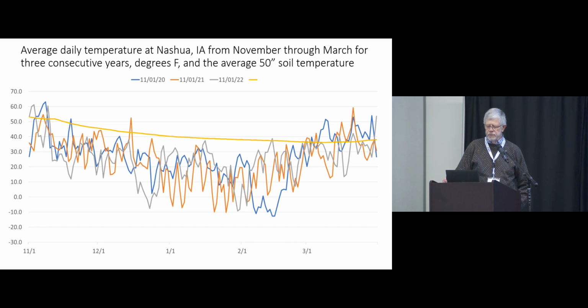And if you had a line for 8 foot, it would be parallel and a little bit above that, but up around 50 degrees there. In Nashua, probably 49 degrees. If you went down to 30 feet, it would be constant. And during the winter, it would give you a little bit higher temperature, and the delta T is very important here. So at 30 feet, normally, wherever you go, that temperature is going to be constant throughout the year.